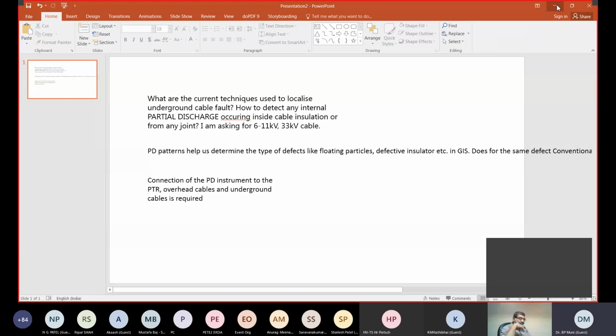Okay, now I will speak technically and not according to the standards. Technically, there might be a slight difference due to the capacitance changes, so that the PD amplitude may not be exactly 5.5 picocoulomb, maybe it's 4.3 or 6.3. But normally it's not the PD amplitude that matters for maintenance. You like to see if there's a PD, and then you like to know where the PD is. The next step is to identify: is it in the joint? Is it a delaminated device in the GIS, and so on? So physically, it's not a big deal.